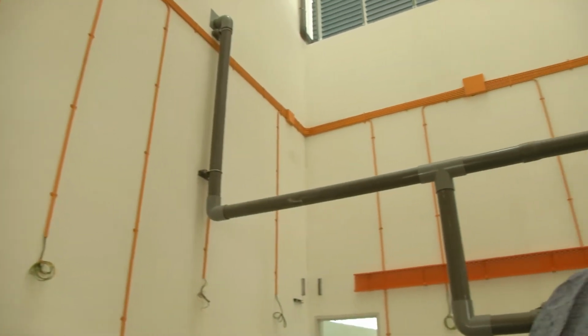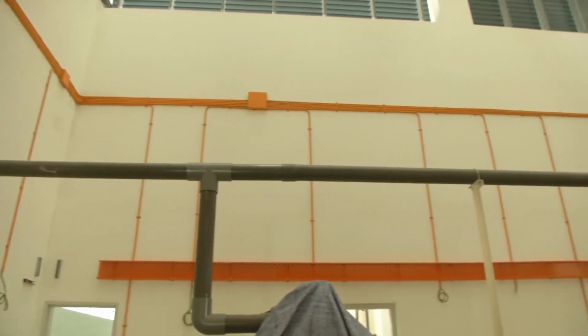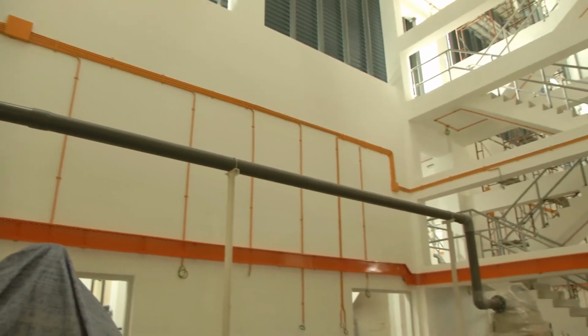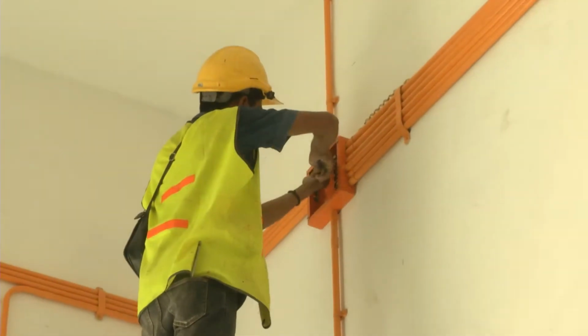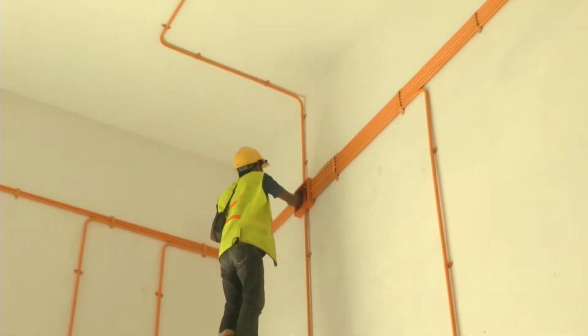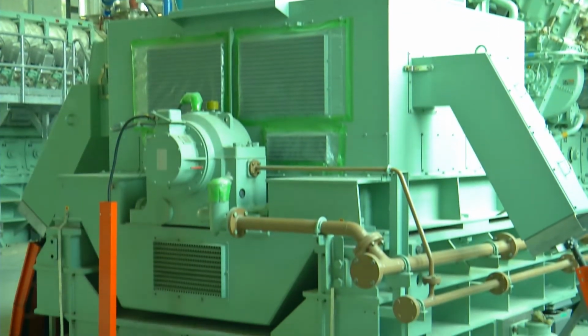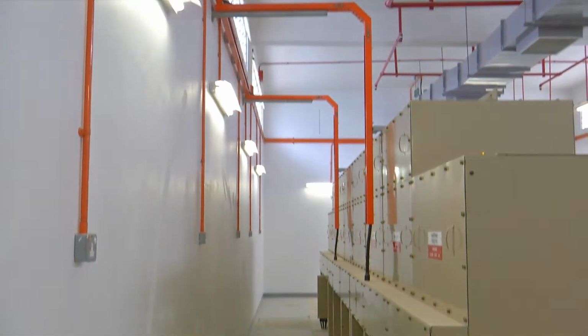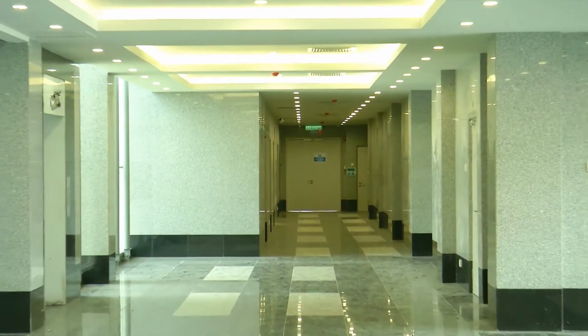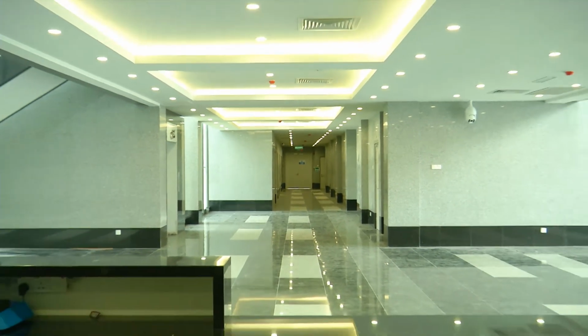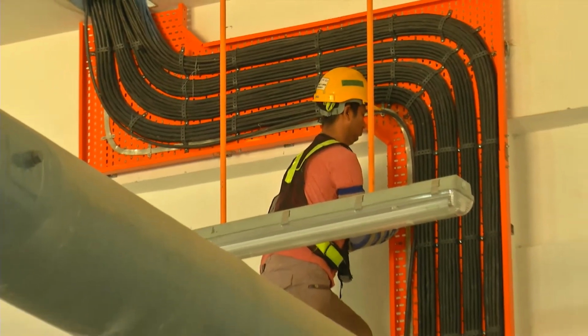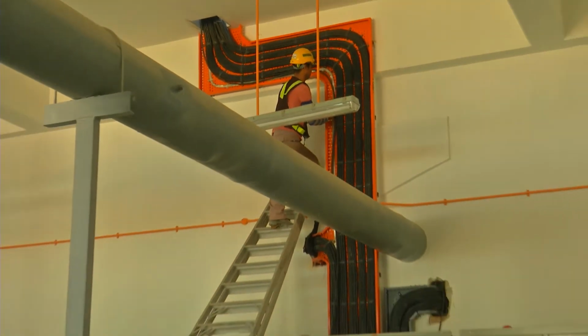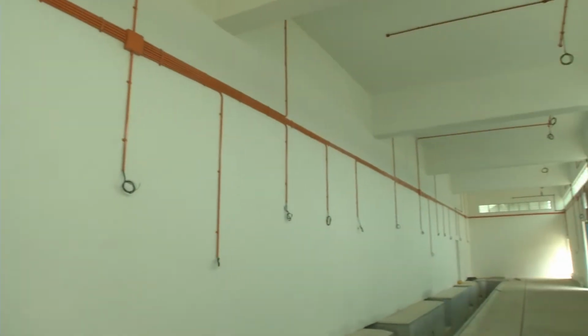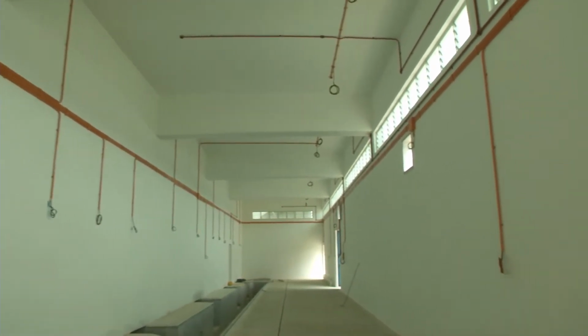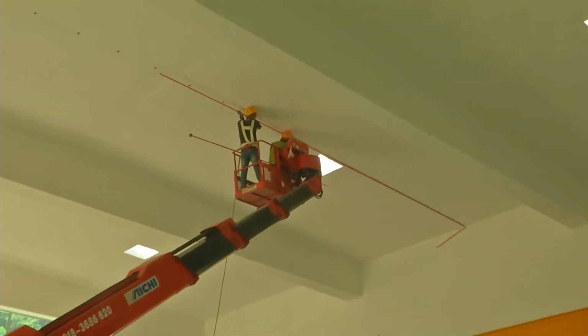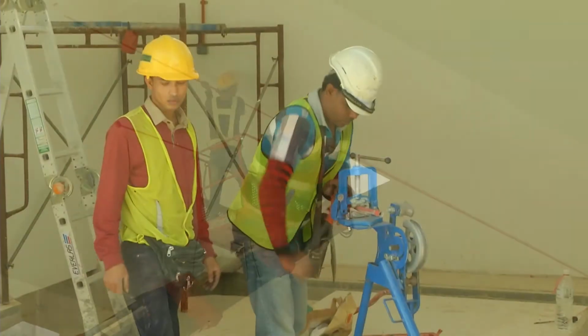The design of the electrical services has taken into account the building form, the characteristics of the building, the occupancy trends and orientation of spaces. The electrical services installation comprises electrical supply, electricity center and main distribution, power distribution services, lighting services and communication services. Conduits and cable tray systems are laid according to the drawing and design intent for each and every structure at the treatment plant facility, to support wires and insulated cables, for the necessary power distribution without any disruption.